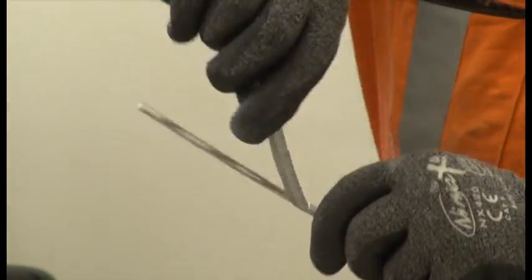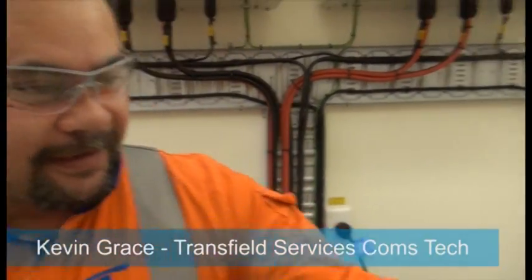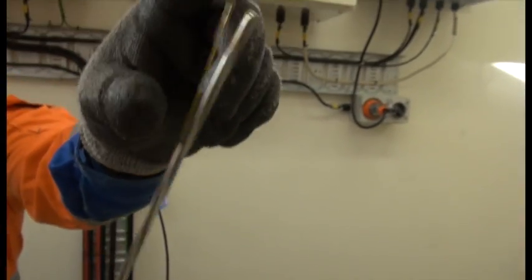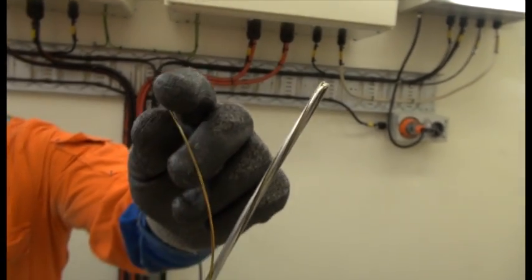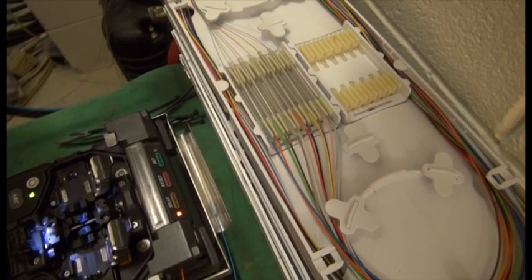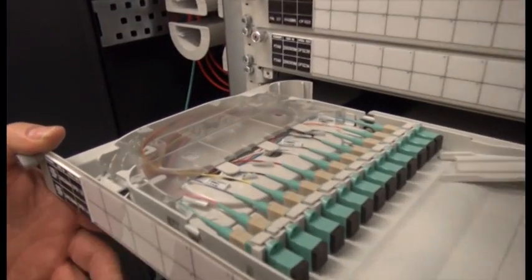Basically just stripping the aluminium sheathing of this. Here's one I prepared earlier - it's just to get at these fibres here. So that's currently what's going across the river at the moment. Once I've stripped them back, I'm going to prep it straight into the FOSC kit there and splice it up to some DI cable that goes directly to a cabinet.